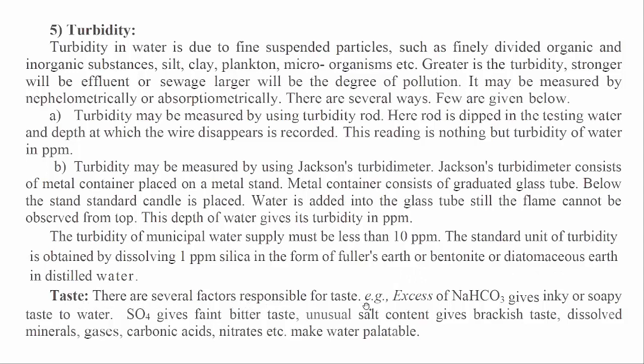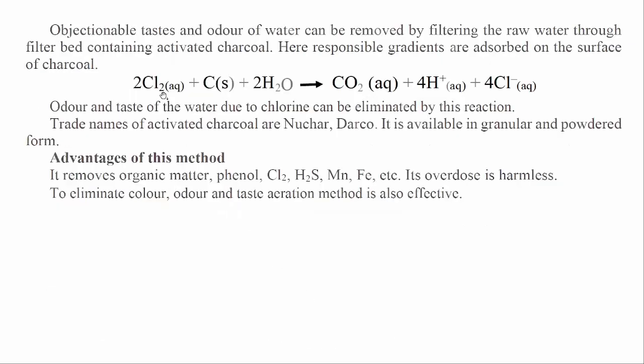6. Taste: There are several factors responsible for taste. Excess of NaHCO3 gives an inky or soapy taste to water. SO4²⁻ gives a faint bitter taste. Unusual salt content gives a brackish taste. Dissolved minerals, gases, carbonic acids, nitrates, etc., make water palatable. Objectionable tastes and odors of water can be removed by filtering the raw water through a filter bed containing activated charcoal, where the responsible compounds are adsorbed on the surface of the charcoal. Odor and taste due to chlorine can also be eliminated by this method.